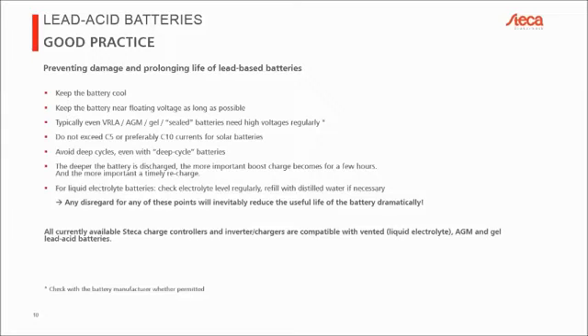So we've looked at the detrimental effects on batteries. Now let's look at the positive side, how you can increase the life expectancy of lead batteries. The first point, keep them cool. Like I said before, every 10 degrees you go up from 25 degrees Celsius, you roughly halve the life expectancy. Then keep the battery near the floating voltage as long as possible. In other words, don't discharge the battery too much. If you can keep it at 14 volts or 13.8 or something like that, then it's happy for a 12-volt battery.